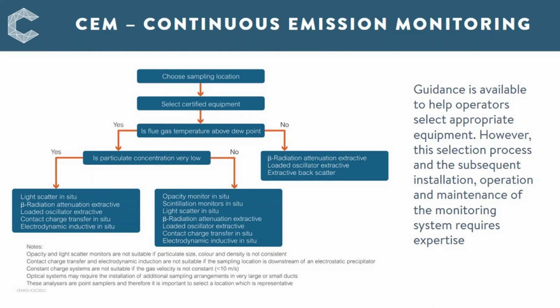They're designed to analyze complex gas mixes coming from a stack, which are sampled at high temperatures, several hundred degrees in some cases. So you've got trace elements, you've got sulfates, you've got acid gases, and so on. And so all at the same time, these machines have to be bolted onto the side of a stack. So selecting and installing a CEM system which is appropriate to the job is actually a complex challenge, and it does require expert guidance.